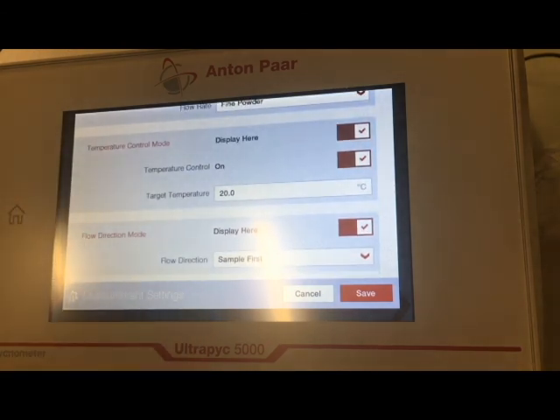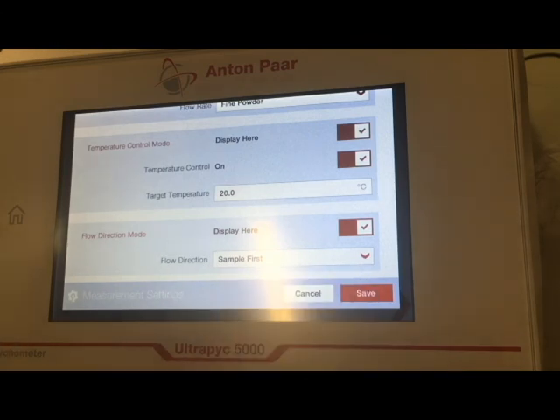In temperature control mode, we're going to tell it whether we want it to control temperature over the course of the test. Typically we do, and this ranges anywhere between 20 and 50 degrees Celsius. Usually we set it to be about 20 degrees Celsius. If you want it to be higher than room temperature, you would change this temperature here, and then click Save. At this point, you would want to wait for 20 minutes before clicking Start on your test to allow the machine and your sample to get to the temperature that you are running at.